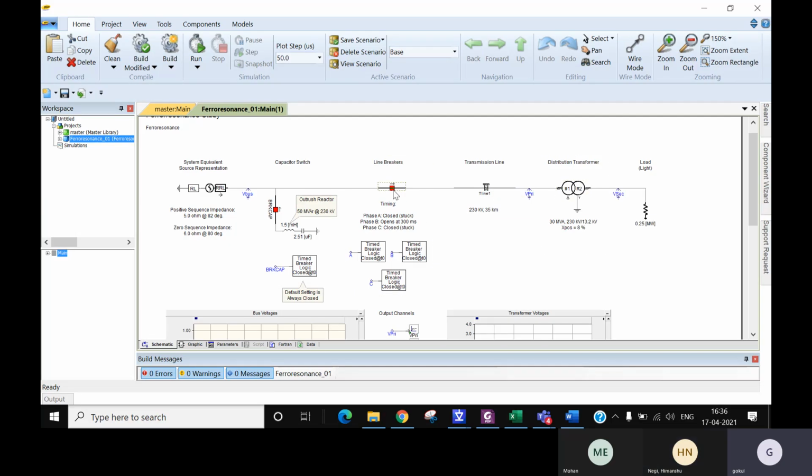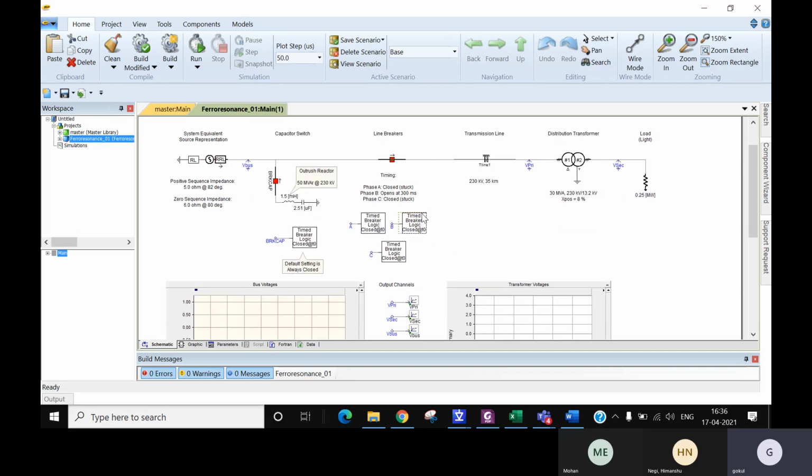But here what they are trying to do is energize both of them together. That is a remote end thing, right? It will not happen. So I feel that's a mistake in this case, but I don't know why they have done it. In our modeling, we are going to energize this transformer. This side circuit breaker, this transformer circuit breaker, we are going to study and implement.